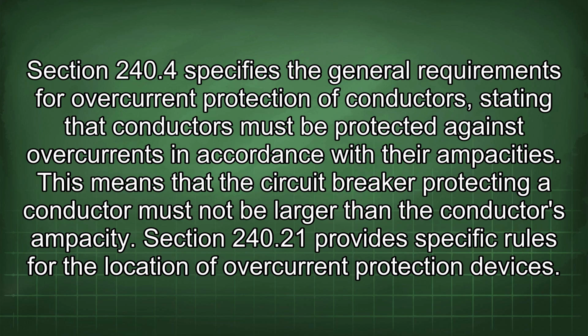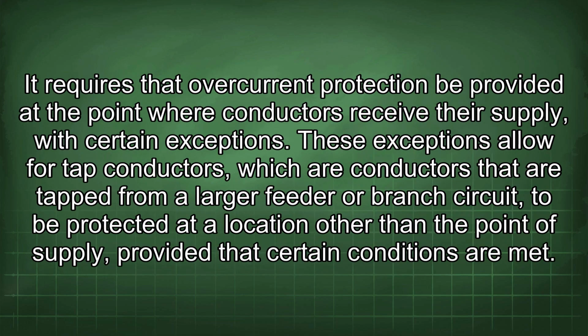Section 240.21 provides specific rules for the location of overcurrent protection devices. It requires that overcurrent protection be provided at the point where conductors receive their supply, with certain exceptions. These exceptions allow for tap conductors, which are conductors that are tapped from a larger feeder or branch circuit, to be protected at a location other than the point of supply, provided that certain conditions are met.